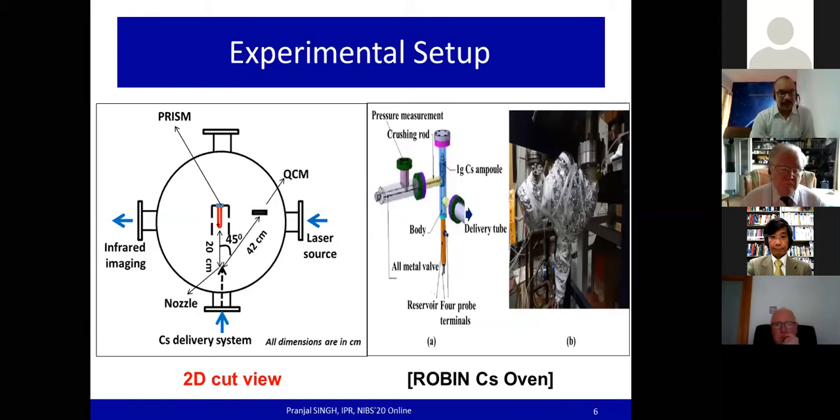There is also an infrared imaging-based system for measurement of the extent of cesium coverage on the filament surface. The cesium delivery system consists of a one-gram cesium ampoule — a glass ampoule containing cesium — and an all-metal valve used for in-situ breaking of the ampoule by a crushing rod. The liquid cesium falls to a reservoir maintained at 100°C, and the evaporated cesium atoms are guided through a delivery tube at 200°C into the vacuum chamber via a nozzle head, which governs the angular distribution and cesium consumption rate.